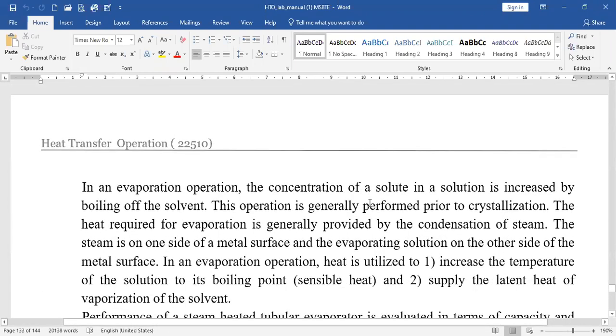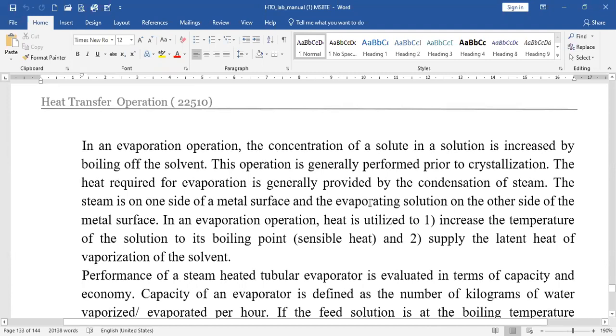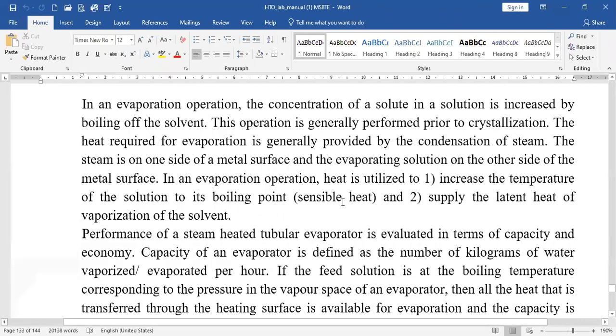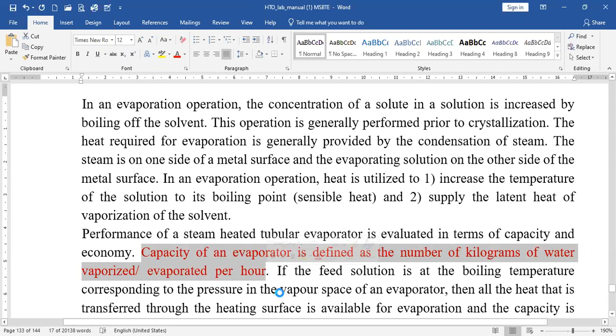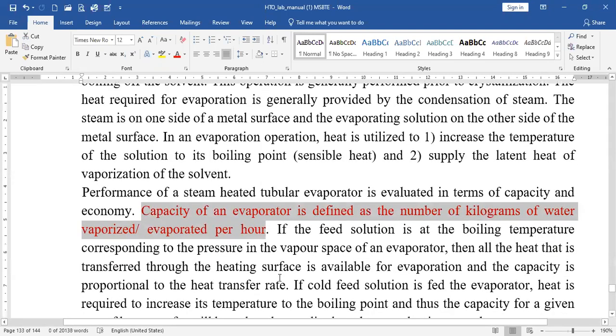The theoretical background: we have already discussed what evaporation is and that the solvent is normally water. Two parameters decide the performance of an evaporator — capacity and economy. Capacity is kg of water evaporated per hour, and economy is kg of water evaporated per kg of steam fed.